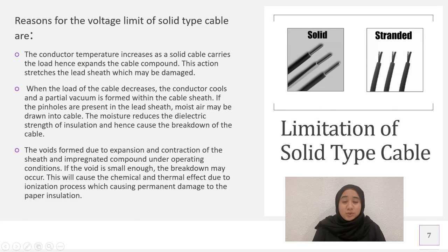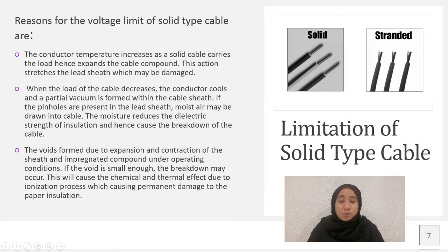The last reason is when there are voids present in the cable insulation. Basically these voids will form due to the expansion and contraction of the sheath and impregnated compound under operating conditions. If the void is large enough, breakdown may occur, causing permanent damage to the paper insulation.